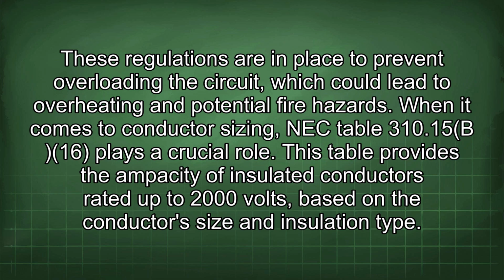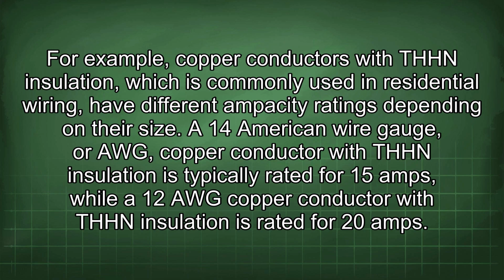When it comes to conductor sizing, NEC Table 310.15(B)(16) plays a crucial role. This table provides the ampacity of insulated conductors rated up to 2000 volts, based on the conductor's size and insulation type. For example, copper conductors with THHN insulation, which is commonly used in residential wiring, have different ampacity ratings depending on their size. A 14 American wire gauge, or AWG, copper conductor with THHN insulation is typically rated for 15 amps, while a 12 AWG copper conductor with THHN insulation is rated for 20 amps.